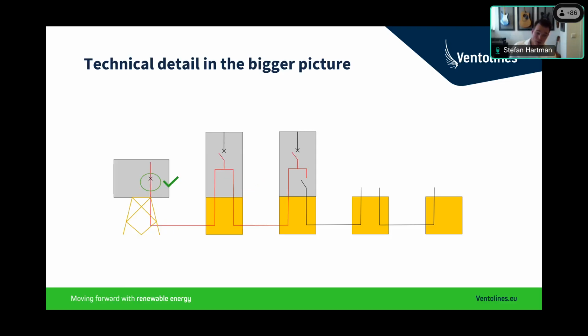Next slide, please. We move back to the offshore high voltage substation. We energize the string. We see now the whole string is energized. Again, responsibility of the employer. And now the turbine contractor, on the next slide, can continue: re-energize the first turbine, hopefully restart the trial run, energize the second turbine, and start their hot commissioning. It is noted here that the moment you interrupt the trial run, if there are any issues in restarting it, it's the risk of the employer, so the time keeps ticking, and potentially you finish the trial run, you run out of time, and it's deemed accepted.